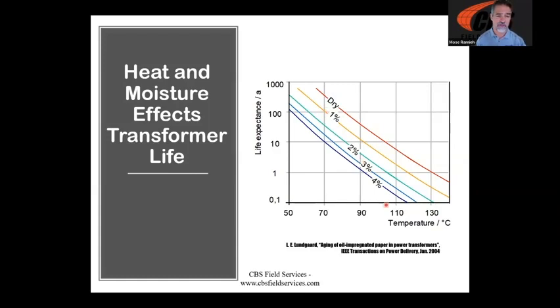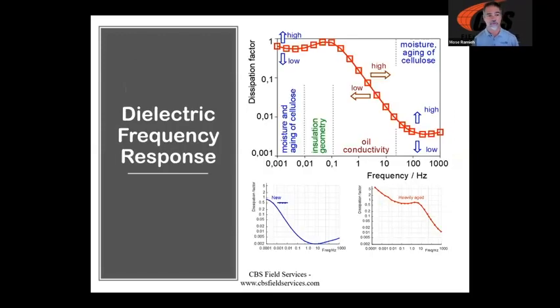And once again, that's a critical asset, right? Lead times on big transformers these days are pushing up over a year. And once again, they're not inexpensive to replace. So keep that in mind. If you do have, or if you are concerned about moisture in your transformer, we can also take that testing up another level using the dielectric frequency response.